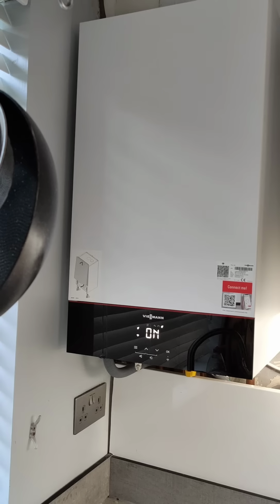On the front, we can cycle through. If the weather comp's set up, we can set the indoor temperature using the up and down arrows. We can then cycle across to the hot water temperature. This will go up to a maximum of 60 degrees. We can have a look at what the system pressure is, and we can turn the eco function on or off. If the eco function is off, then the hot water will heat up quicker, it'll get to the taps quicker, but it will burn a little bit more gas.